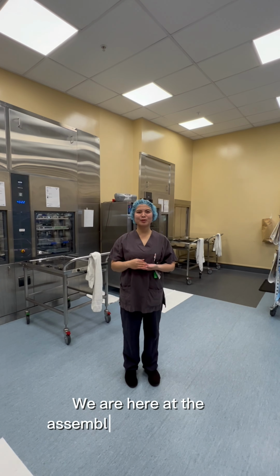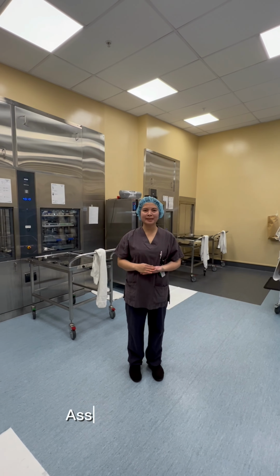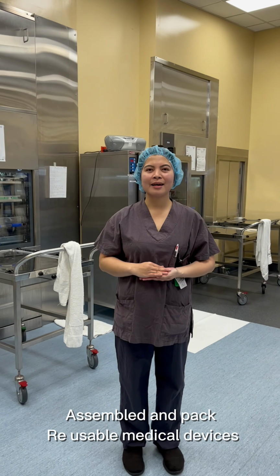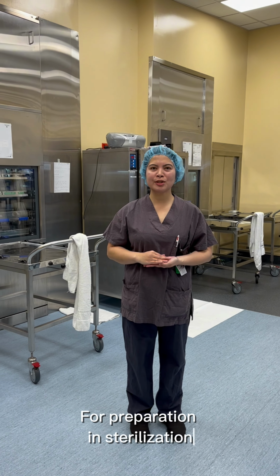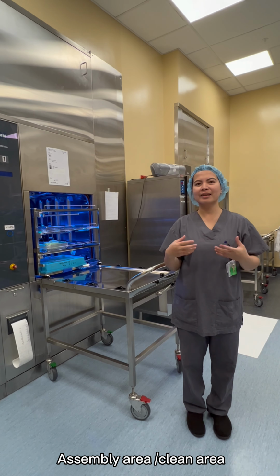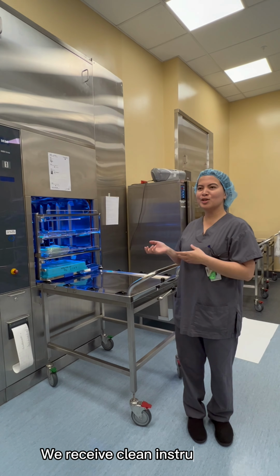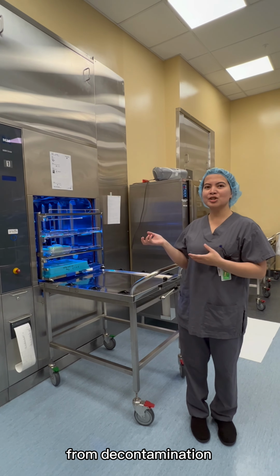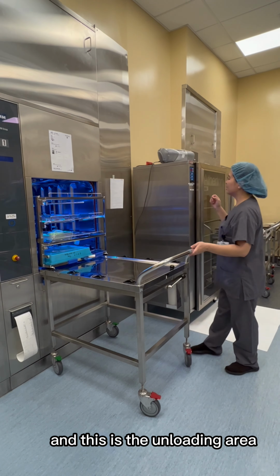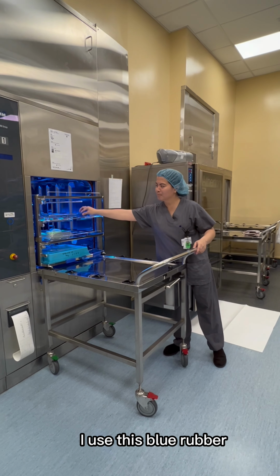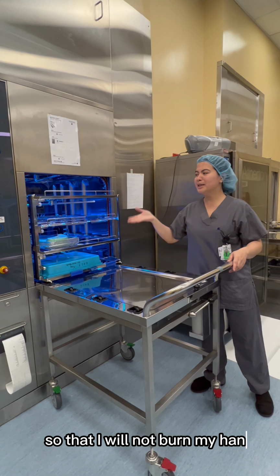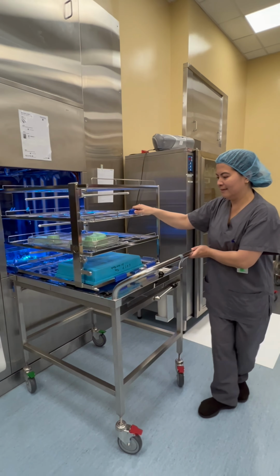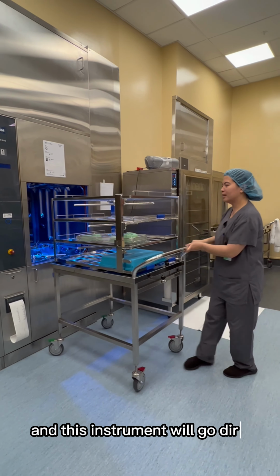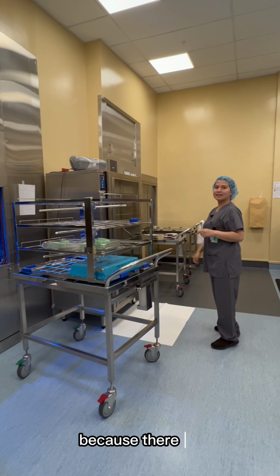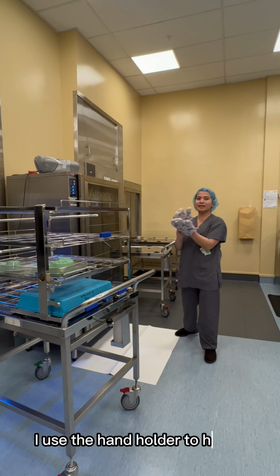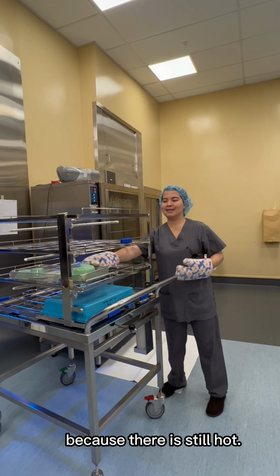We're here in the assembly room where we inspect, assemble, and pack reusable medical devices for preparation of sterilization. We're here in the assembly area, or clean area. Here we receive clean instruments from decontamination, and this is the unloading area. In unloading, I use these blue ones so that I will not burn my hands. And this instrument will go directly in the dryer because they are still wet. I use the pot holder to hold them because they are still hot.